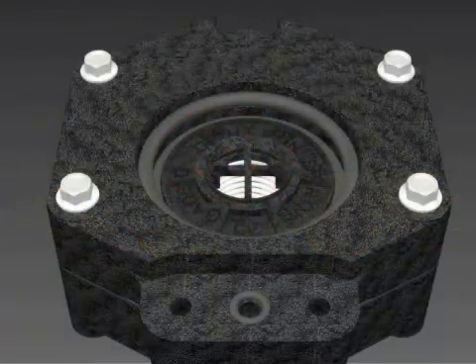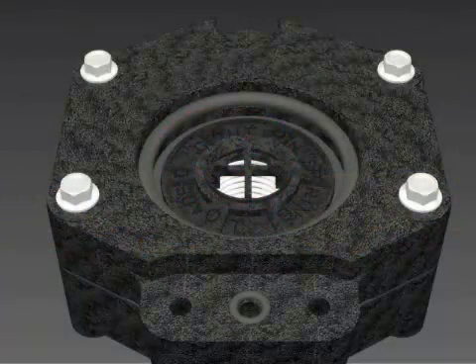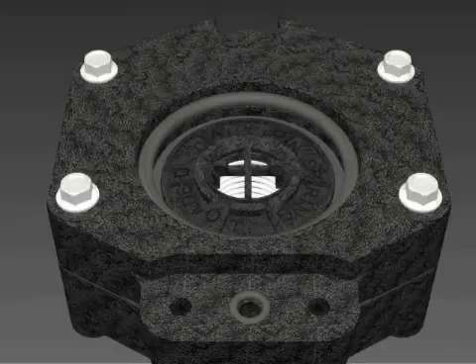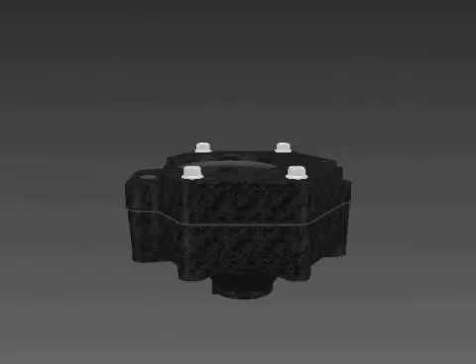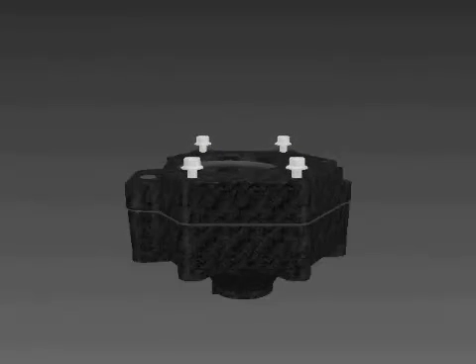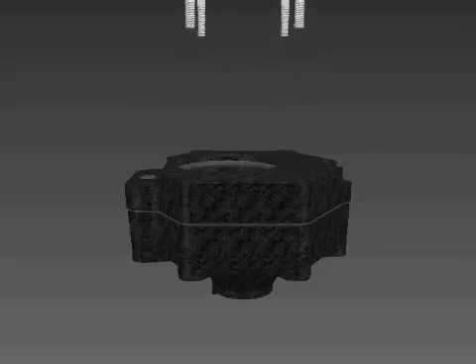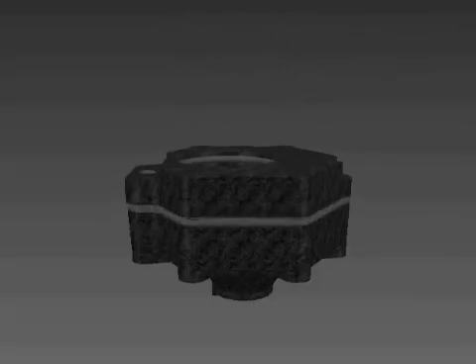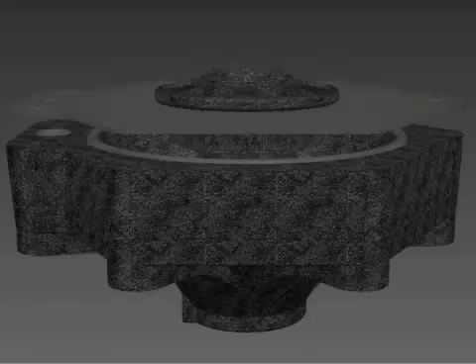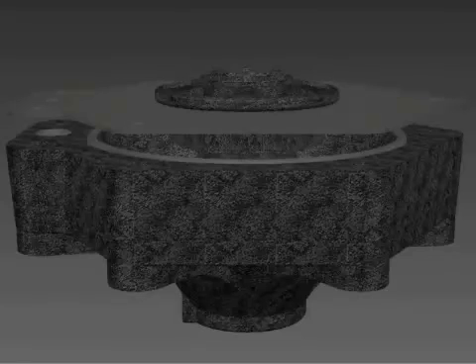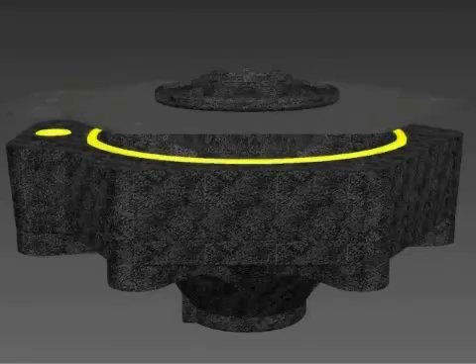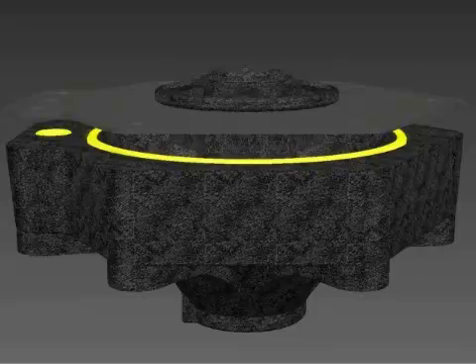The seat is showing through the top hole on the relief valve assembly. You will inspect the sharp edge of the seat with your finger for any damage. To disassemble the relief valve assembly, remove the four bolts that hold the two halves together. Pull the relief valve cover and flange apart. Make sure you do not lose the large and small O-ring between the diaphragm and cover as you open the assembly.